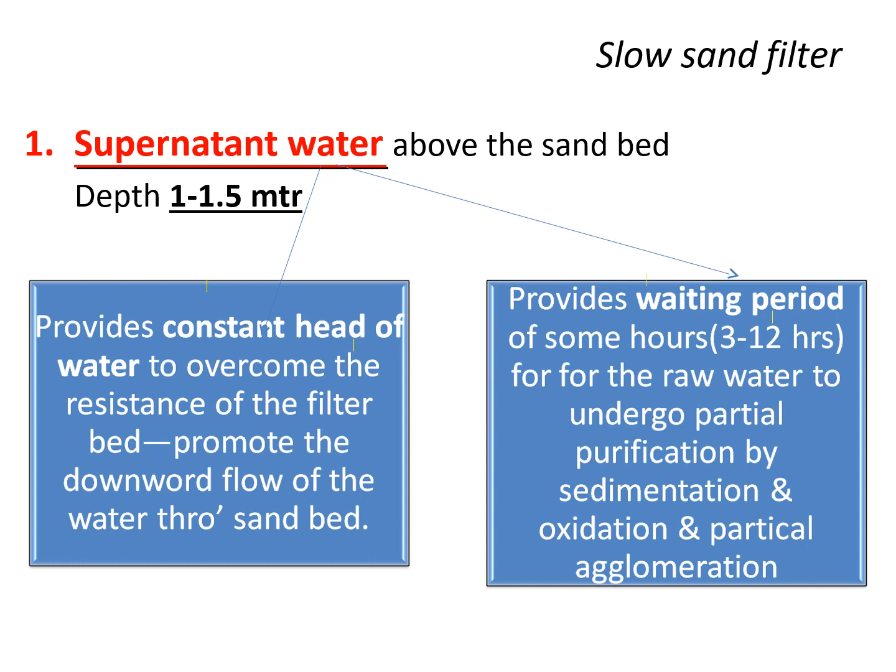The supernatant water lying above the sand bed provides a constant head of water to overcome the resistance of the filter bed, promoting downward flow of water through the sand bed. It also provides a waiting period of 3 to 12 hours for the raw water to undergo partial purification by sedimentation and oxidation. Storage alone purifies water to nearly 90 percent, so even before filtration begins, storage helps in partial purification through sedimentation and oxidation.